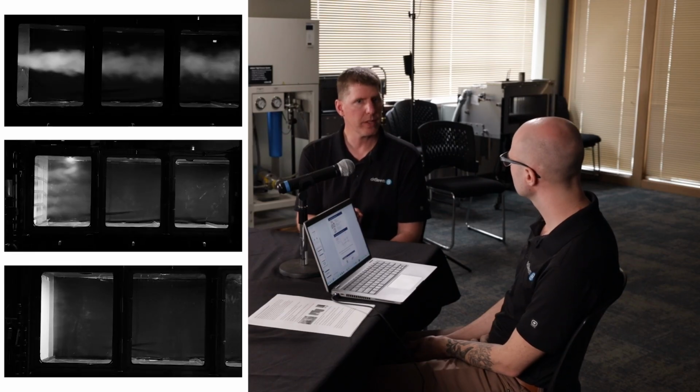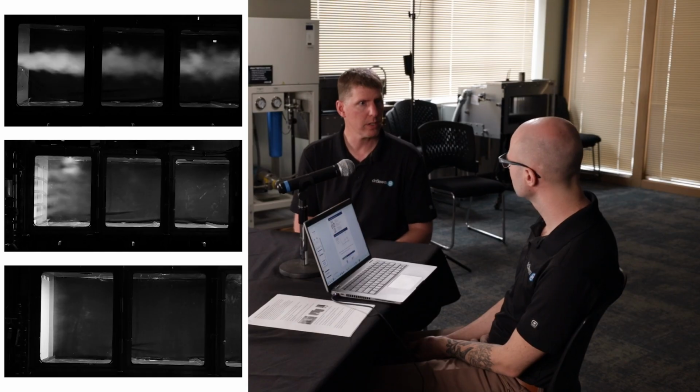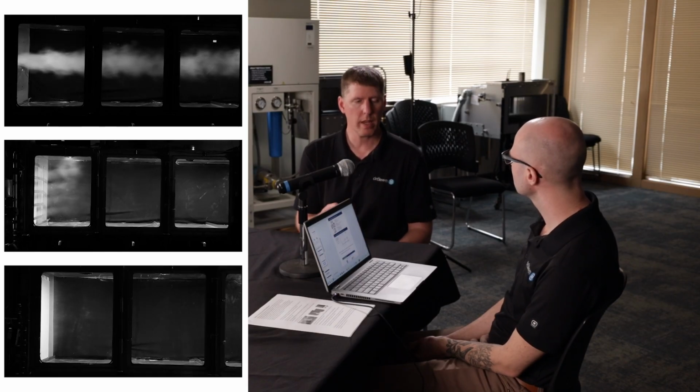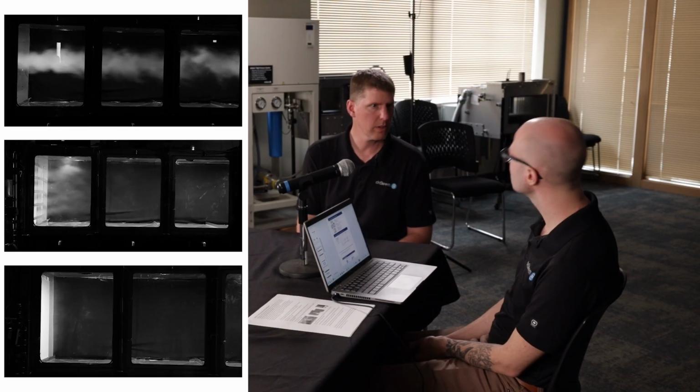The warmer the air, and that's why we said that before a heating coil wasn't necessarily a good spot, because the air is cooler. It's closer towards saturation. So the warmer the air, the faster it's going to dissipate. Understanding as well how much moisture I'm adding, if the steam has more contact with the airstream, it's going to dissipate faster. So that's another key piece. In terms of distances, you can do it as little as 6 inches.